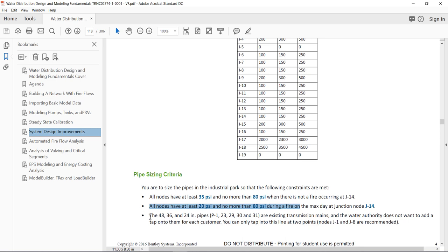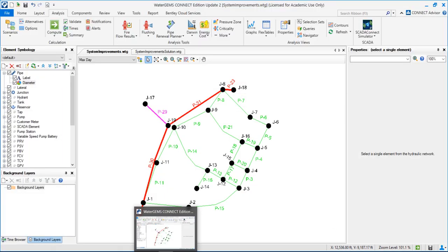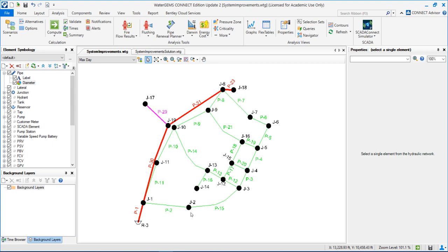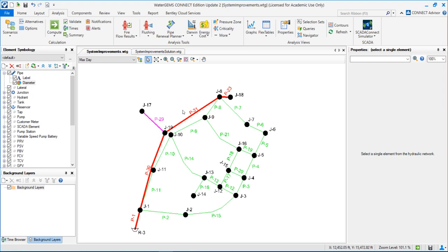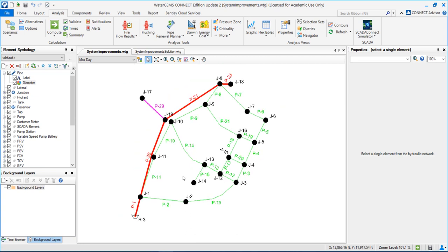The other requirement is that the transmission mains — all the red and pink lines — we will not change the size. They already exist. So mainly we will need to change the size of the green pipes. The green pipes are connected to the main line through J8 and J1. Usually, one approach when we want to design a network is to start upsizing the pipes from upstream, the source of water, to downstream, then sizing and upsizing the pipes.